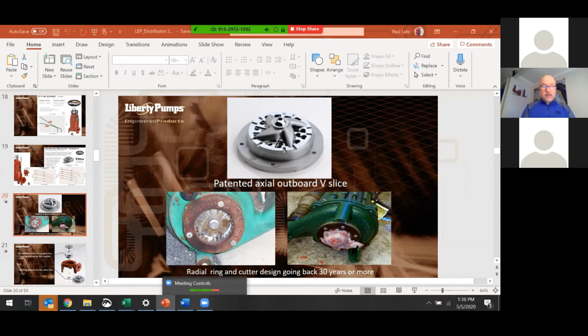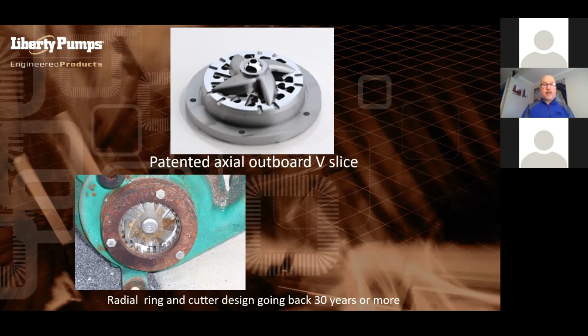Here we're just showing the difference between our patented axial outboard V-slice design versus the old style radial ring and cutter design, going back 30 years or more. We came up with this design probably 10 or 12 years ago, because of all the testing that we did. We were finding that the radial ring and cutter design would pull in a lot of material at one time, and then the floats would tell the pump to shut off, and it might have a huge wad of material lodged up under it, and there wouldn't be enough starting torque to really get that pump started again.